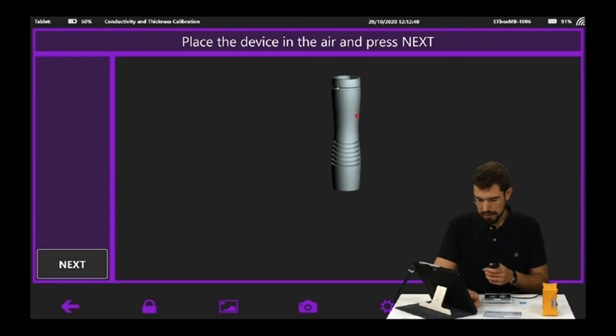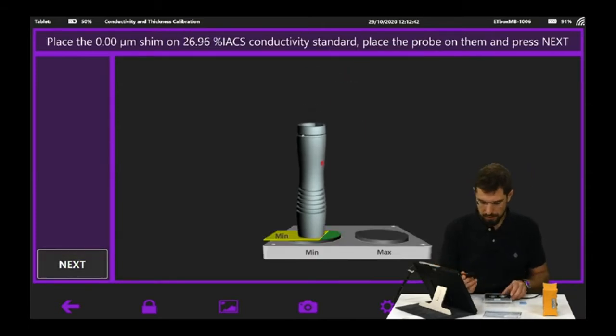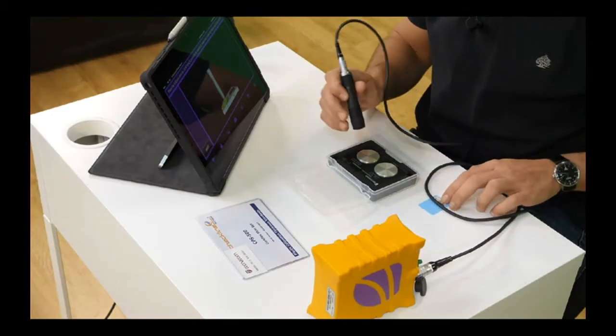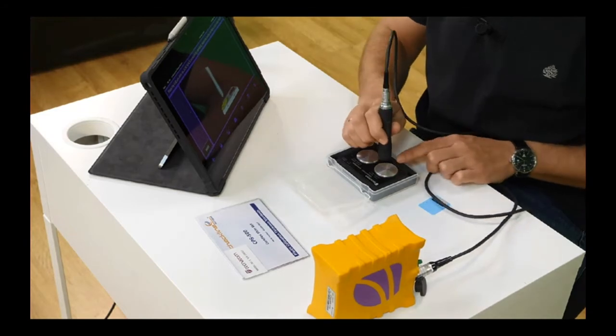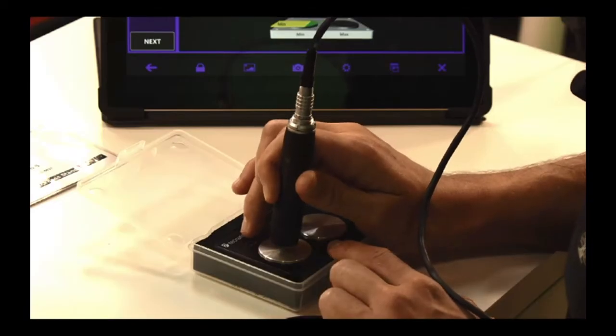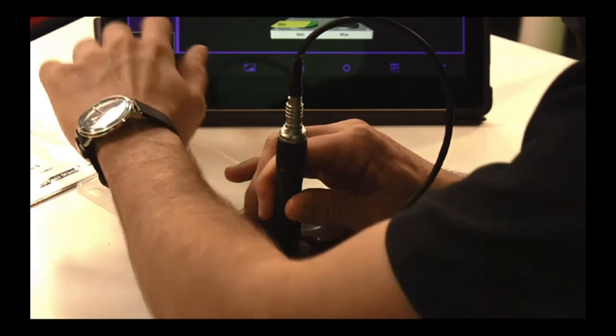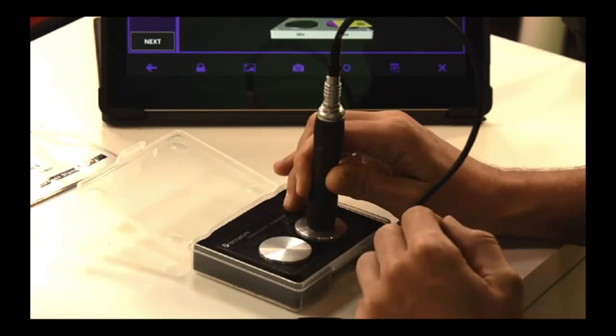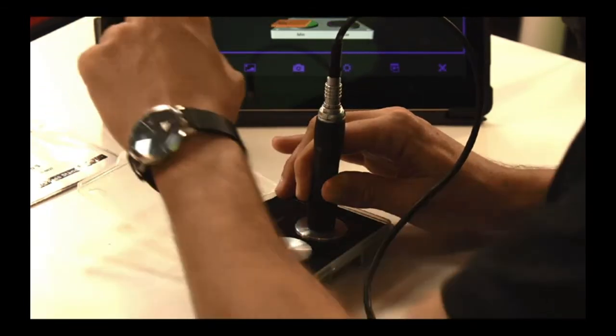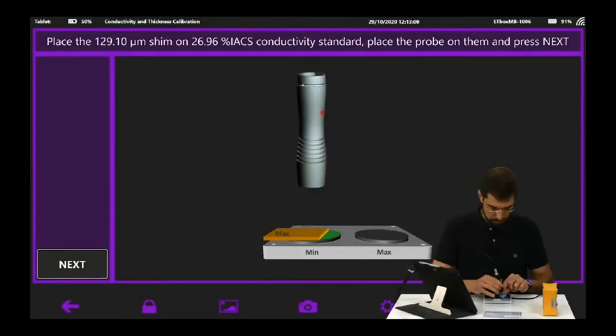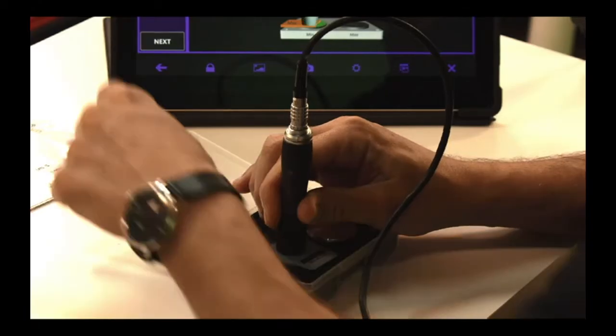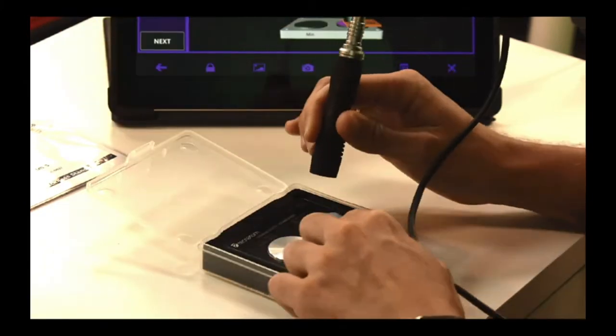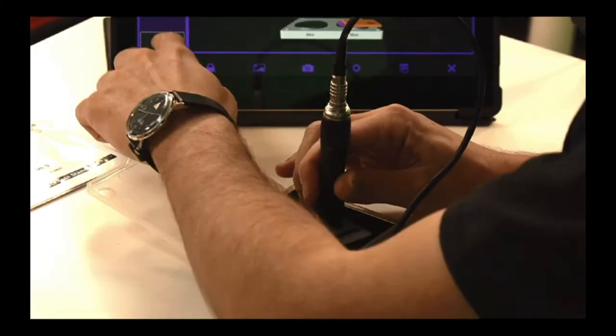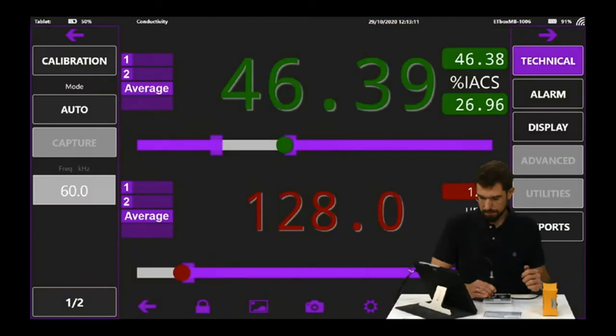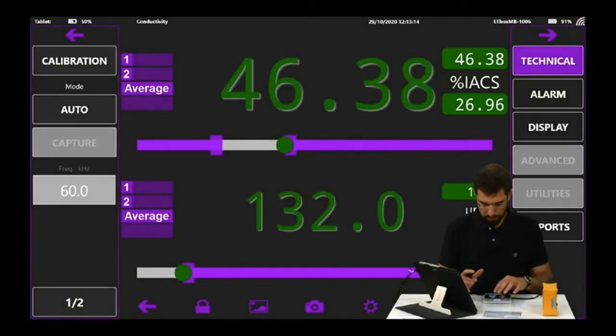In this case, we put the probe on the air to get a reference. It tells us to use the pattern with the lowest conductivity and lowest thickness. We hit Next, lower conductivity and higher thickness, Next, and higher conductivity and higher thickness. Okay, so this is how easily we've done a calibration for our conductivity and thickness test.